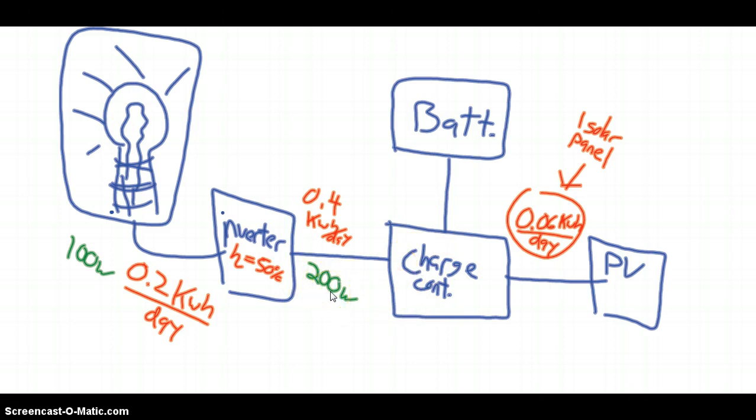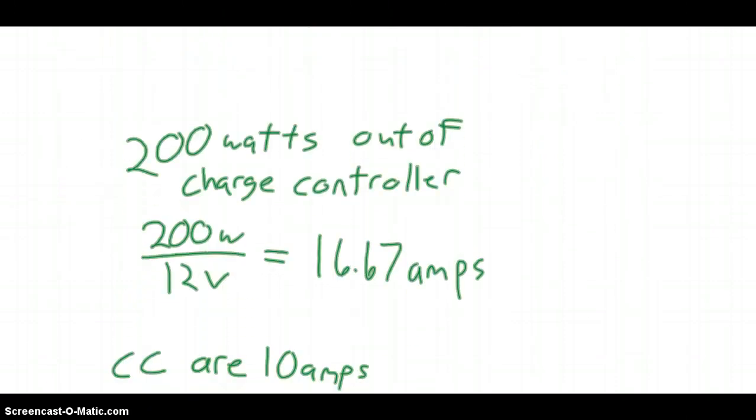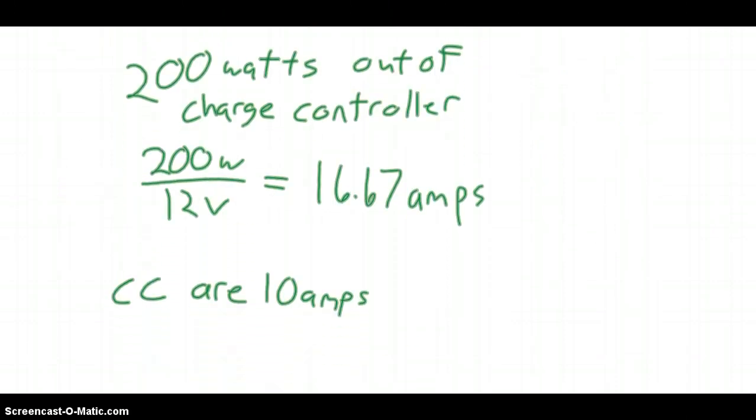Now, in our systems, everything is 12 volts, except for after the inverter. So the charge controller, the battery, the PV panel, everything here before the inverter is 12 volts. So that's what we're going to assume. So the first thing we're going to figure out is how many charge controllers do we have to buy. So if we have 200 watts out of the charge controller, that's 16.67 amps. And our charge controllers are 10 amps, and I didn't write it here, but you'd have to buy two charge controllers.